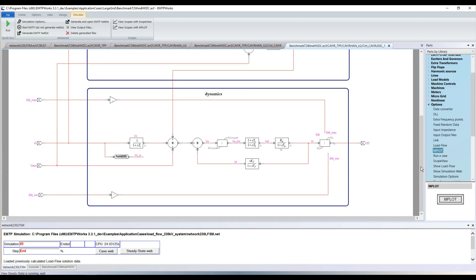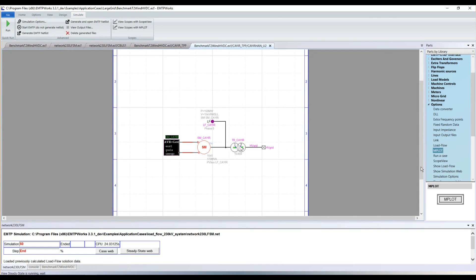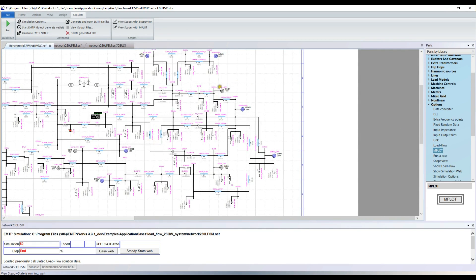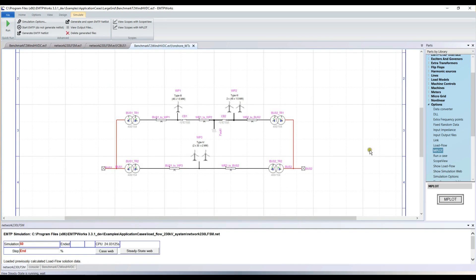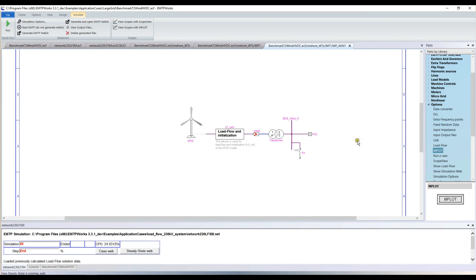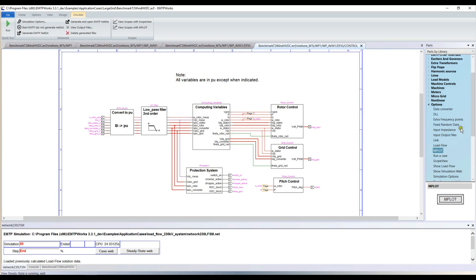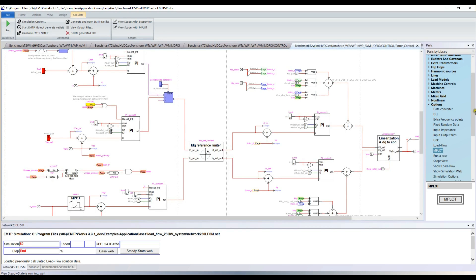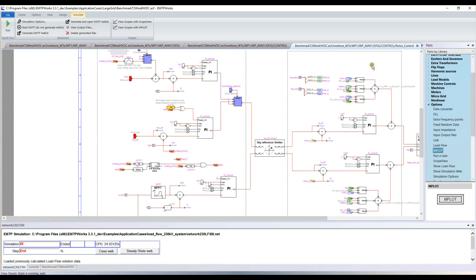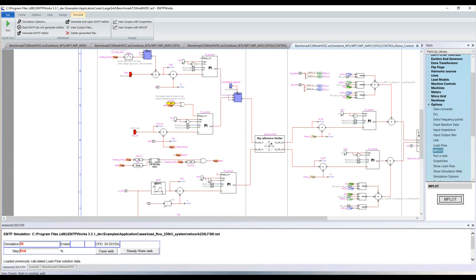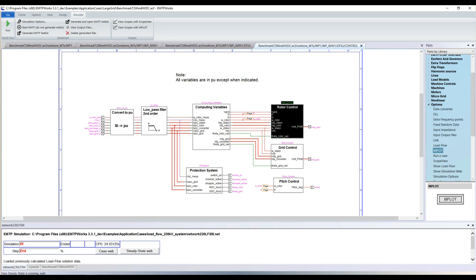The grid also includes onshore wind parks — type 3 and type 4 — in very detailed models with transformers, the wind turbine itself, rotor control, and grid control including all the different loops: proportional-integral for the power loop, reactive power loop, voltage loop, and DQ0 current loop — outer and inner loops — all modifiable as needed.